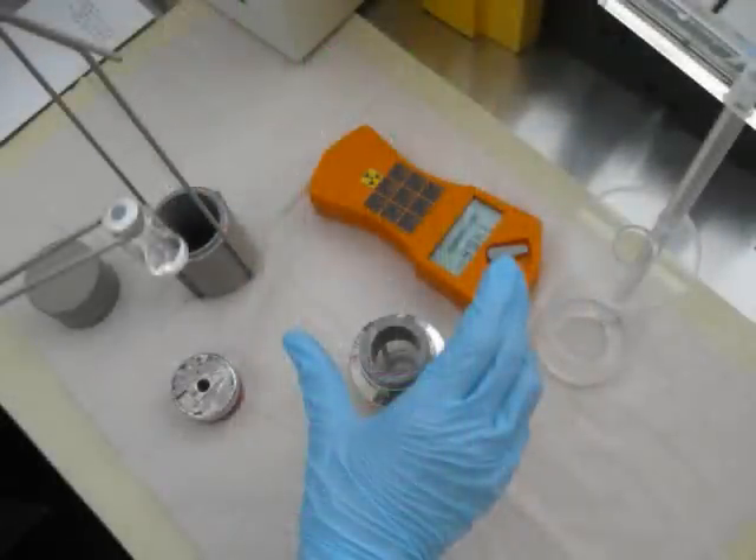Here, in the middle and to the left, you can see our tiny bottle of eluate. It doesn't contain very much activity — just 1.3 GBq. That is enough for, depending on the scan, 1 to 15 patients — really depends whether they are getting a thyroid scan or a heart scan. And it's still quite a lot: 1.3 GBq is 1.3 billion decays — 1.3 billion gamma rays being emitted every single second. And that's quite hot.